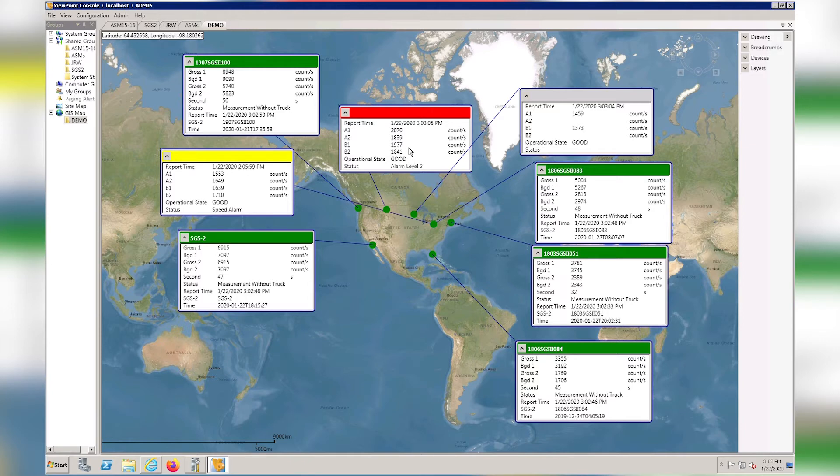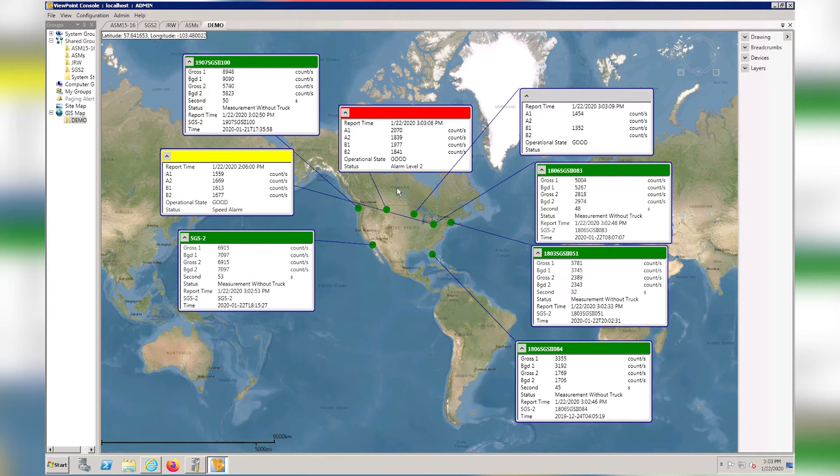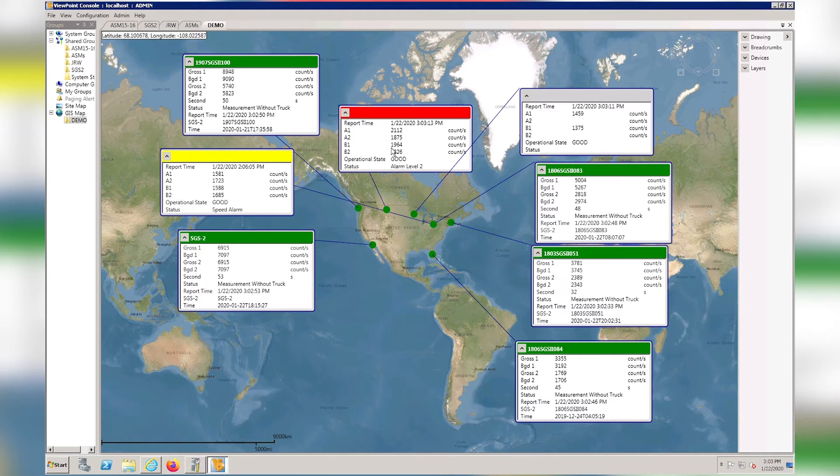This one is in alarm state, and you can see that the backgrounds are pretty low on these three detectors. They're all displaying in the high 18 and 1900s, while this one is in the 2100 range. So that detector must be getting an excess amount of signal based on the alarm thresholds.